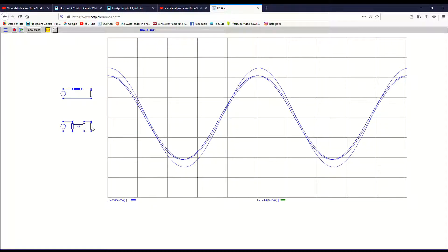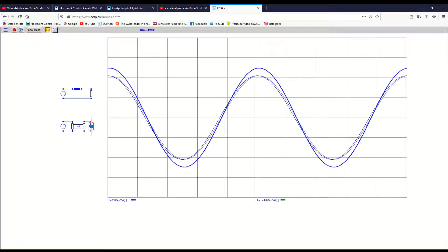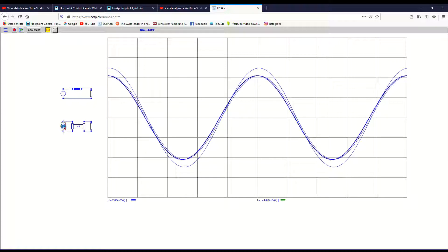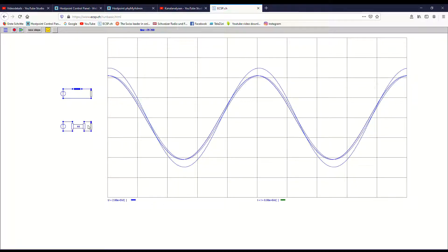Where you see that at the low load, that means a high resistance at the load, the voltage at the load is much, much higher. We talk here maybe about 50% or even more higher than the source voltage. And this is really now due to the reactive power in the line, and this we will have to compensate in the future.